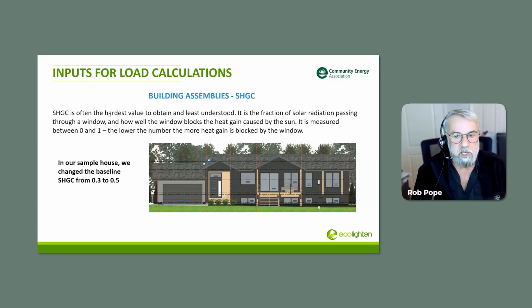It's a good question because it's the hardest value to get. A lot of times you get the R value or U value of the windows, but not the solar heat gain coefficient. You cannot proceed with a load calculation without the solar heat gain coefficient. It's very, very critical, and it's very often the hardest thing to obtain. Sometimes you've got to pull teeth to get it, but it's necessary.